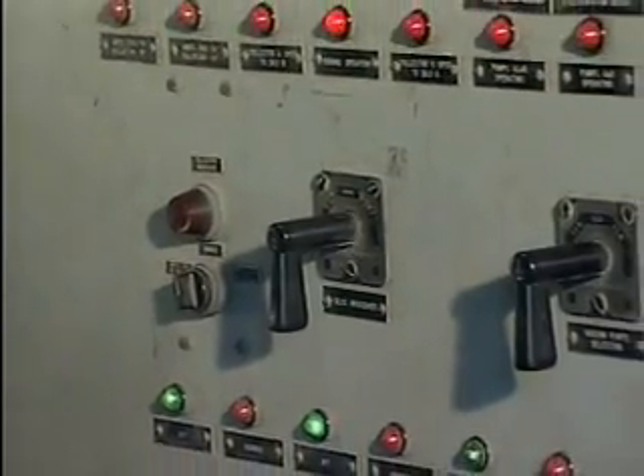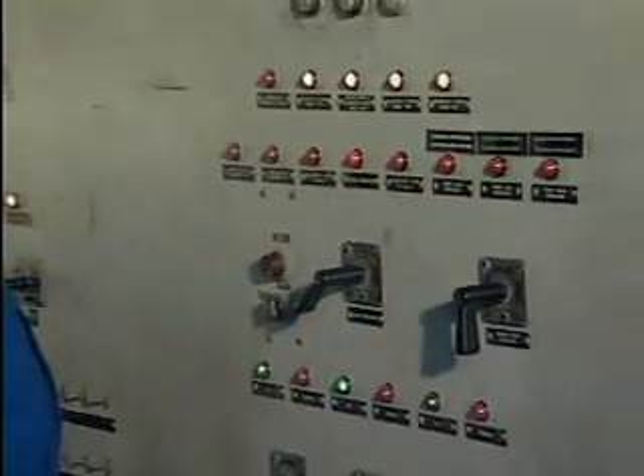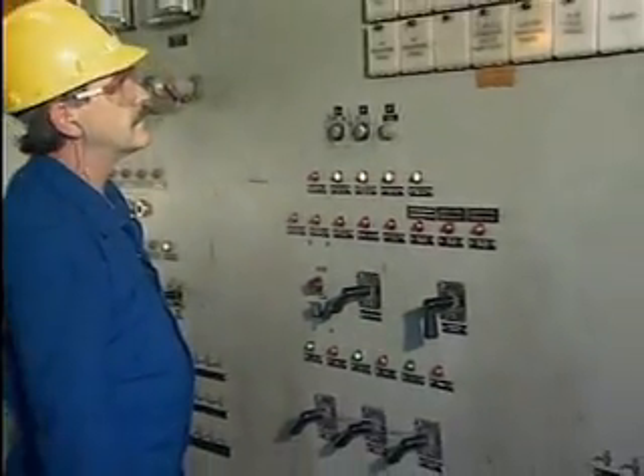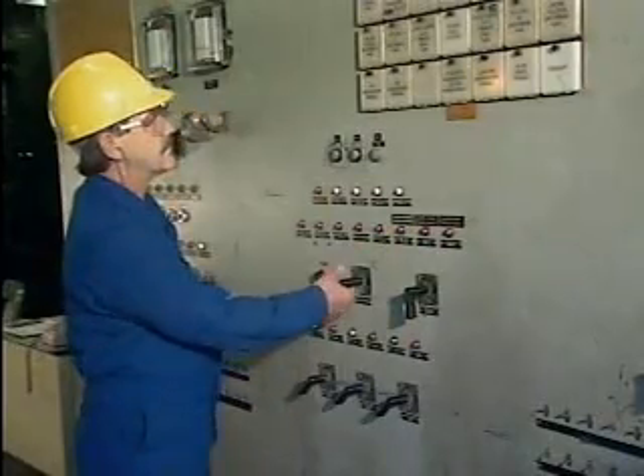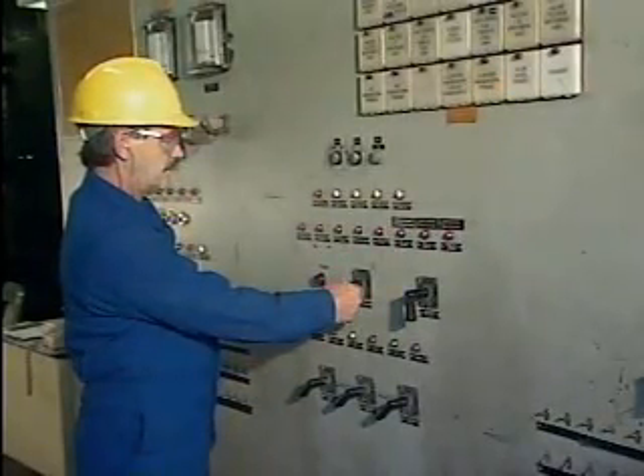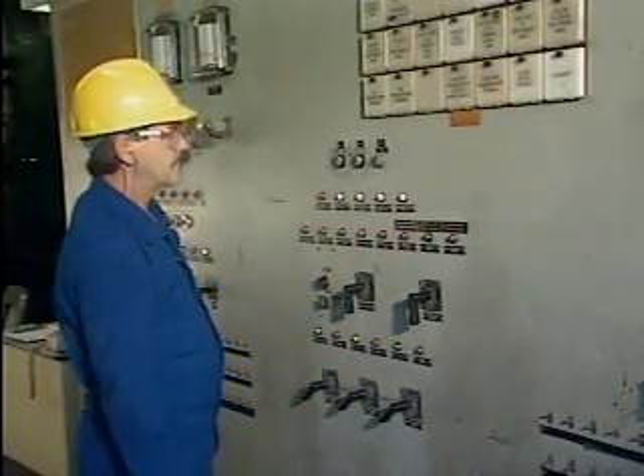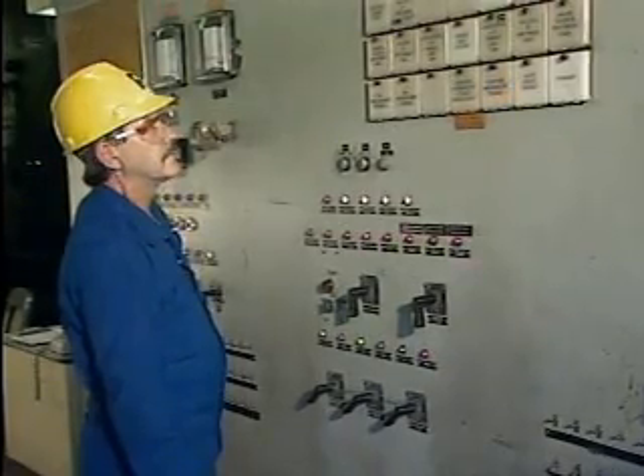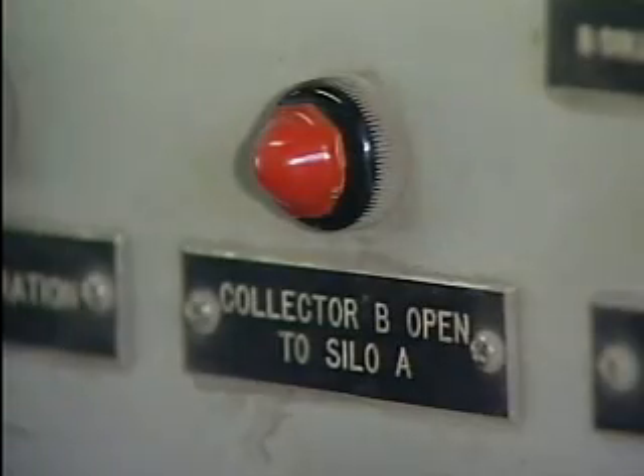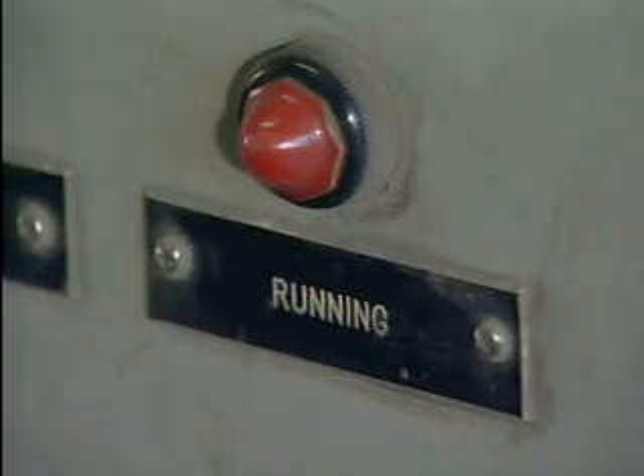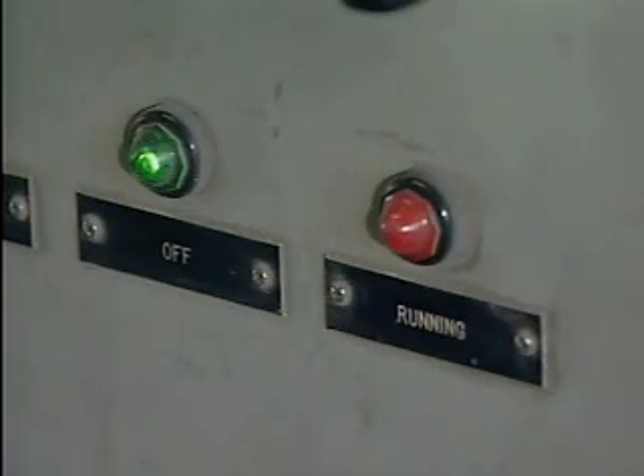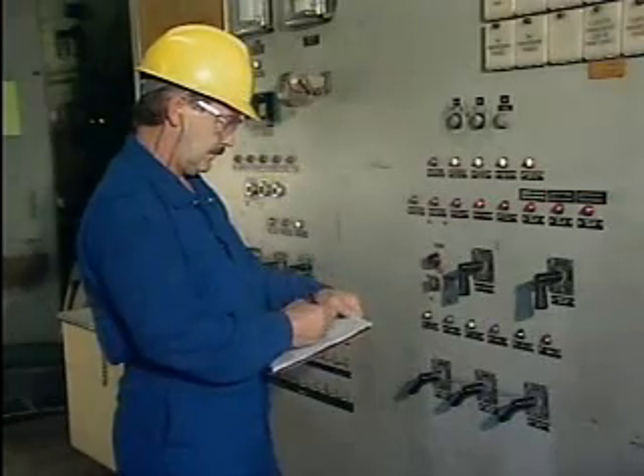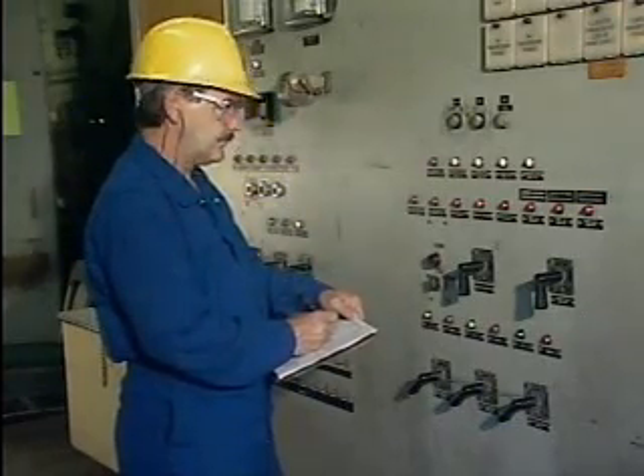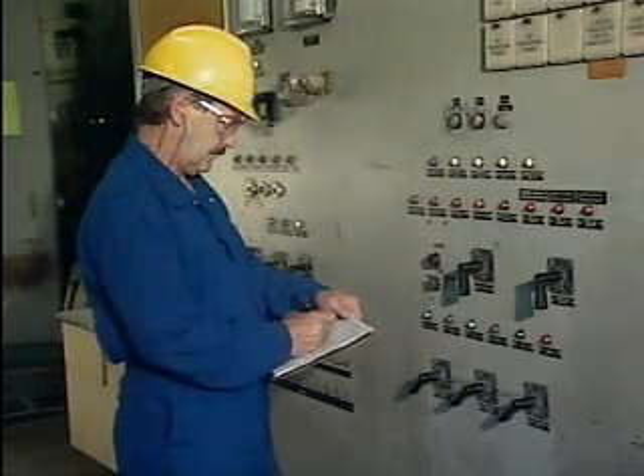The electrician attempts the same procedure that the operator went through to start up the process, paying particular attention to the control panel's indicator lights. It's possible to gather a lot of information about a problem using the devices that are already in place. The indicator light for the appropriate silo crossover valve did not come on. The indicator lights for the B system's vacuum pump and pressure blower did not come on either. The electrician knows that this process is designed to operate only when all of its valves and other equipment are set up properly.